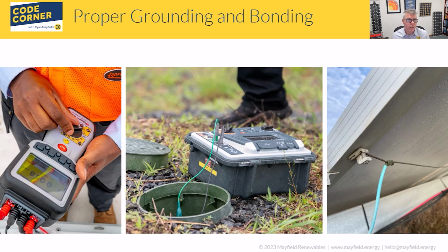One of the benefits of tools like the DLRO is that they sell spools that let you have a 100-meter distance between the two. So this is a great tool where you can get set up at one spot, maybe at your inverter pad or something like that, and you can spool out and go check continuity. You can check the bonding, how good the bonding is between the electrical components that the equipment grounding conductor is connecting.